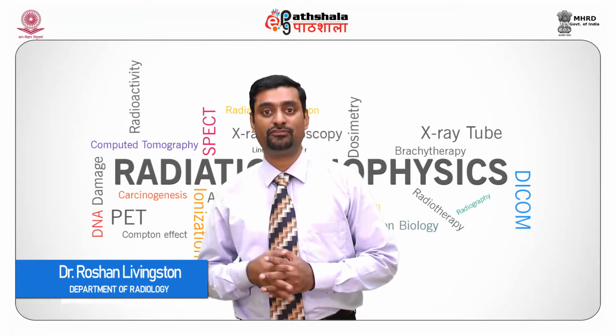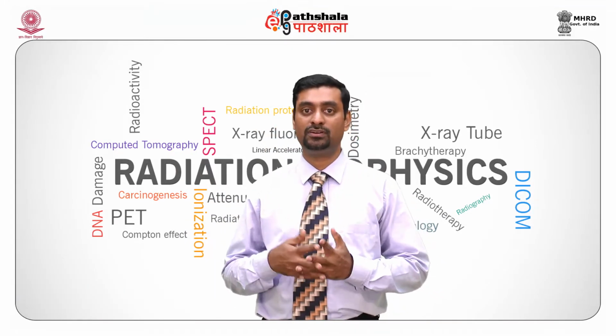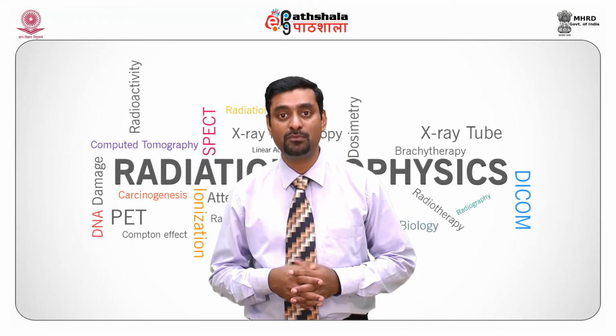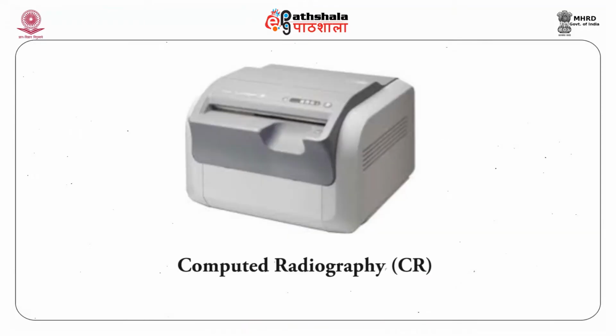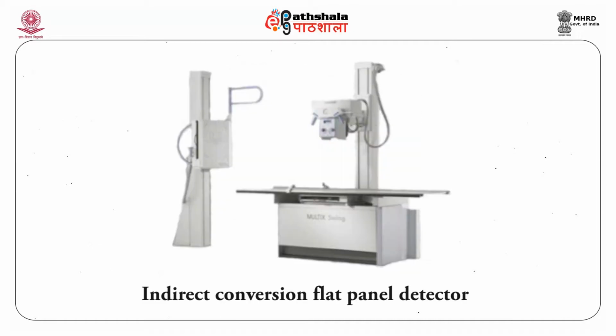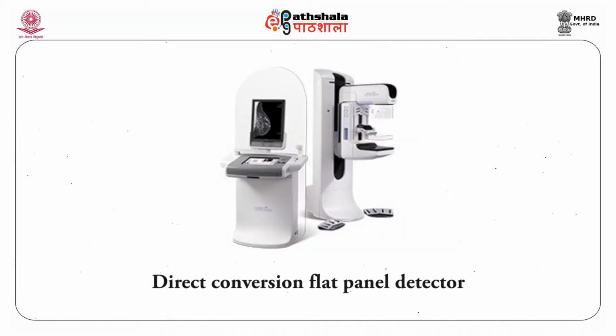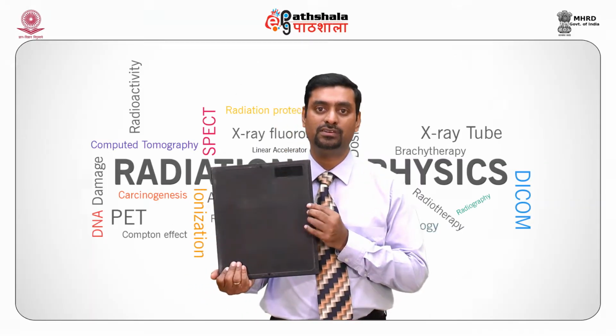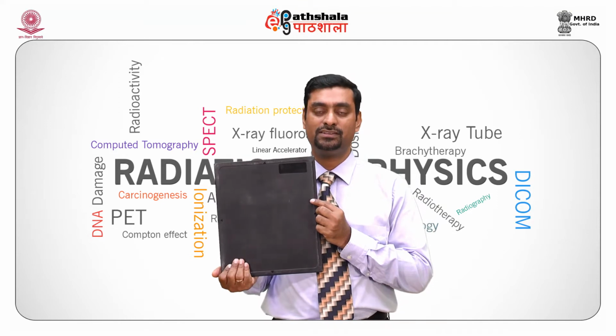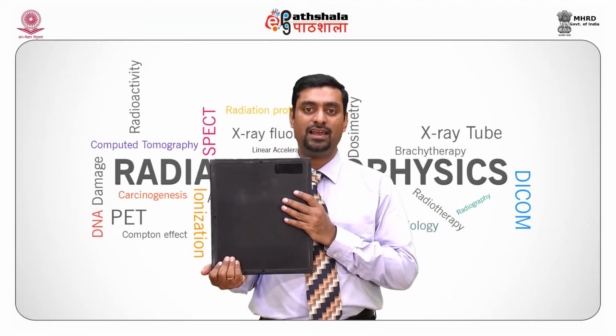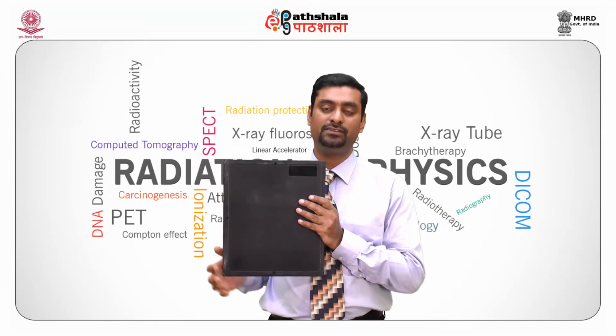The various types of detectors that are used for routine radiography as well as mammography include computed radiography, indirect flat panel detectors, as well as direct flat panel detectors that can be used for mammography purposes. Let's consider looking into this computed radiography cassette. This cassette has its detector inside.